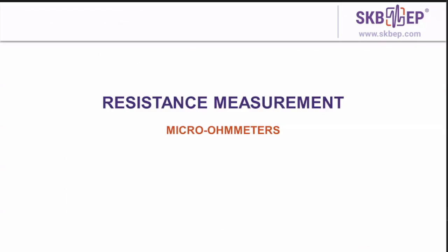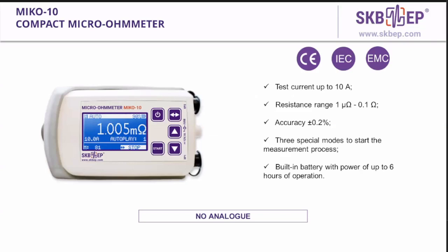The next group is resistance measurements, micro-ohmmeters, a subgroup of ohmmeters. The first here is MIKO-10, a compact micro-ohmmeter. It has a small size and a good test current up to 10 ampere. That is enough for most cases in contact connections. MIKO-10 has a built-in battery with power of up to 6 hours of operation. It has an energy-independent memory of up to 100 recordings, which is sufficient for an overall and complex test of a transformer substation. It has 3 special modes to start the measurement process.